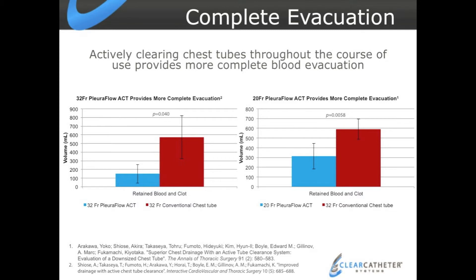In the lab, we started out looking at a 32 French PleuraFlow versus a 32 French conventional at the amount of blood in a hemothorax model — we could get far superior drainage with the PleuraFlow. But where I was really excited, and we published this in the Annals of Thoracic Surgery, was that we could get better flow and drainage with a 20 French than we could with a 32 French conventional using the active clearance technology.